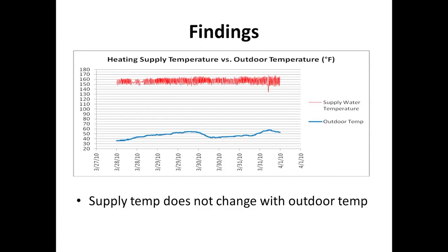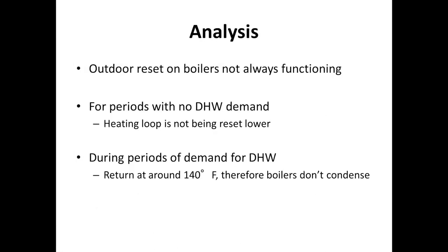For this, what was important in this chart, only showing the supply water temperature, was that we noticed right away the supply water temperature was always right around 150. It wasn't adjusting too much based on outside temperature. Generally, it was staying the same. This building did have outdoor air reset, and this boiler should have adjusted based on outside air temperature. So we saw that the outdoor reset for the building wasn't always functioning, and whether there were periods of high domestic hot water demand or low domestic hot water demand, return temperature was never dropping below 130.